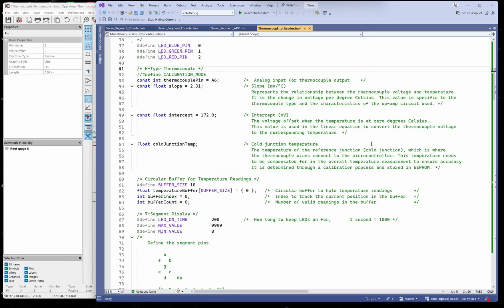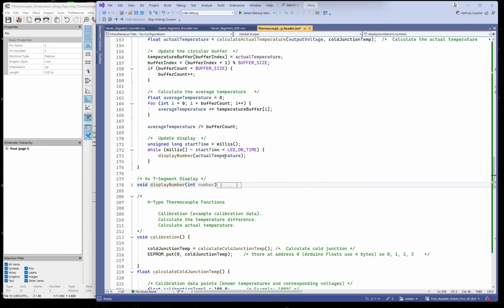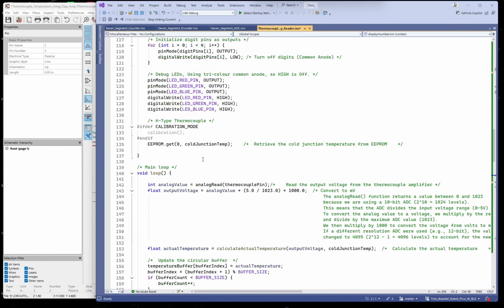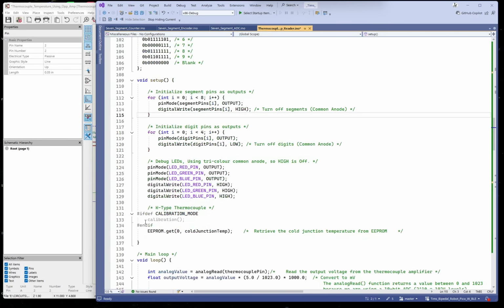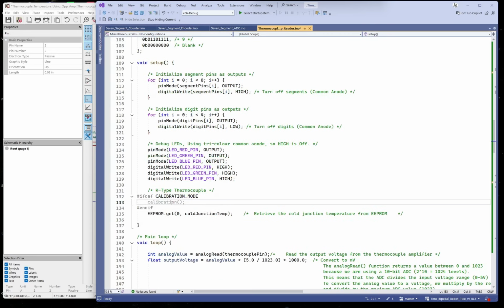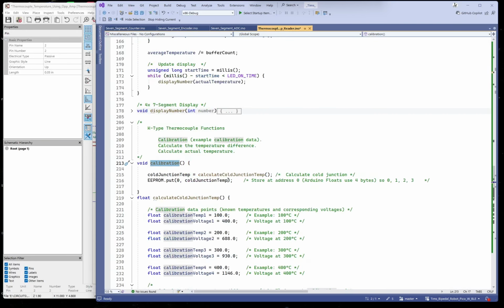So if I comment that out, and then we can see down here, where are we? Setup, yeah, there. We can see that it's now grayed out because we're not going to use it. The compiler knows not to use that anymore. So if we're going to do calibration, we go to calibration. In calibration, what we need to do is we need to know what the cold junction temperature is. This is what we're finding. So there's another function, calculate cold junction temperature, which is down here, this one.